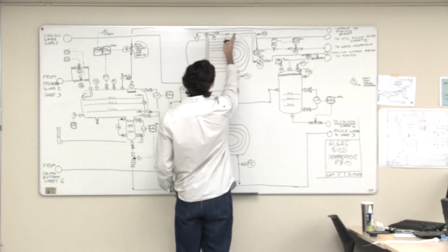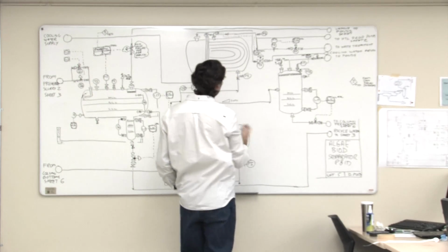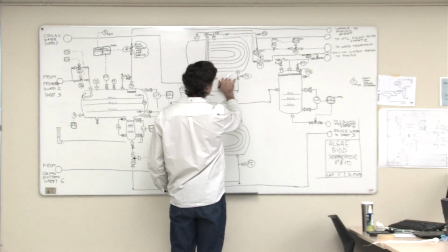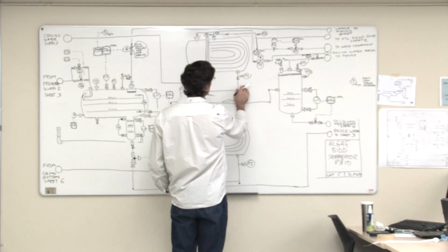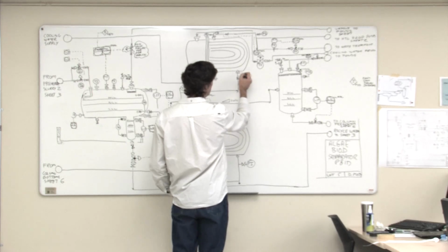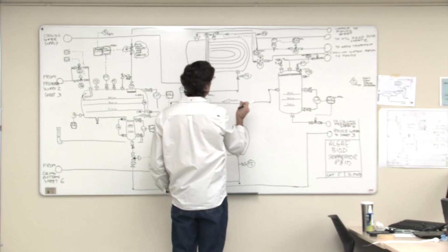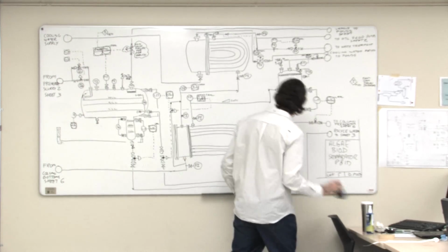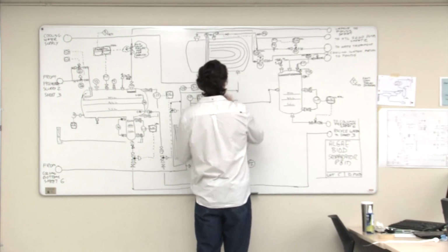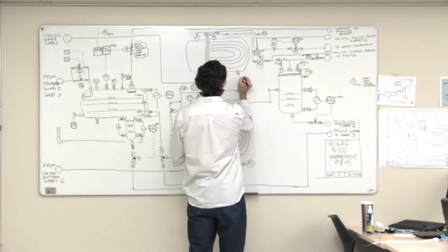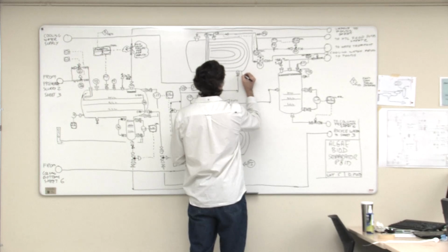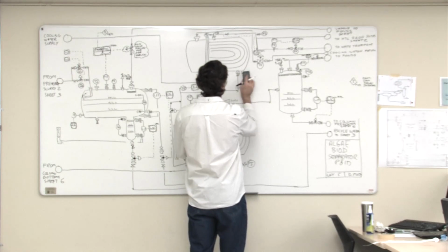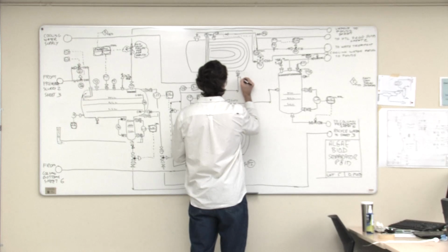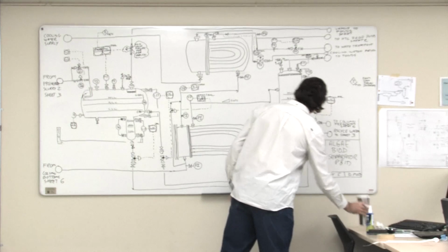So if you put the PI on the downstream side of the block valves, in a sense, you're not really getting a true measurement of DP across the heat exchanger. You could actually put the PI on the heat exchanger itself. So that might not be a bad idea. Actually, I like that idea better. So that allows me to put the block valve right on the flange of the heat exchanger. And then we'll just put a PI right on the heat exchanger. No, I don't like that either. That's going to cost money.